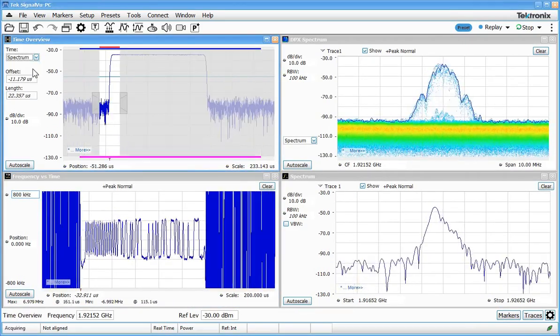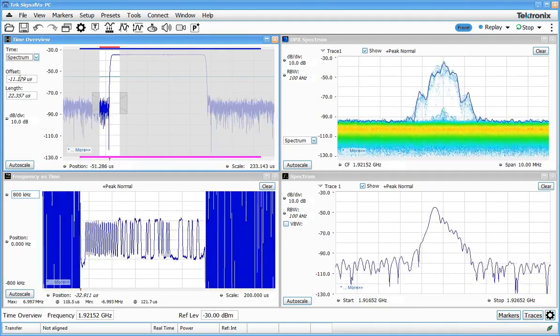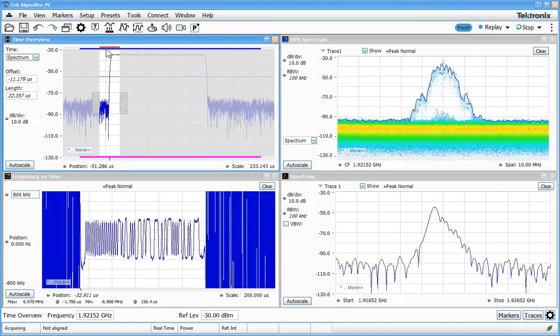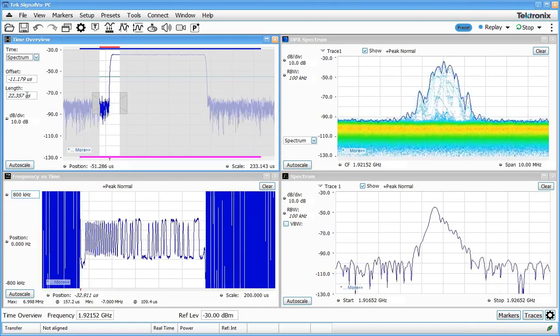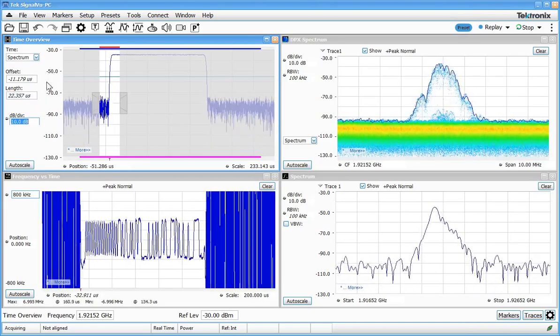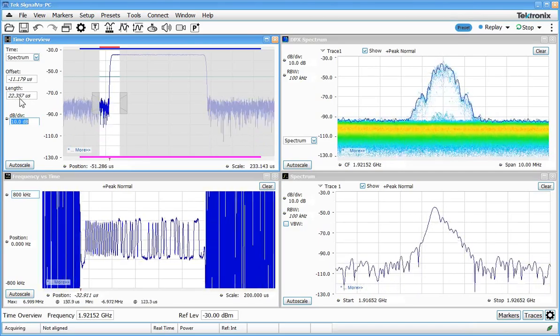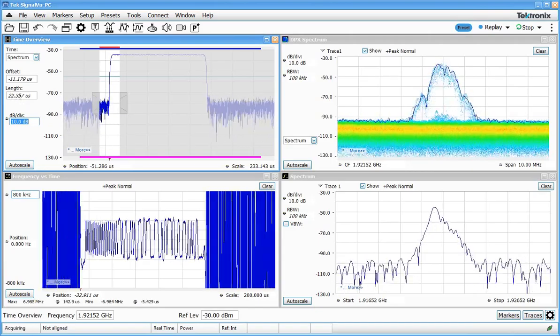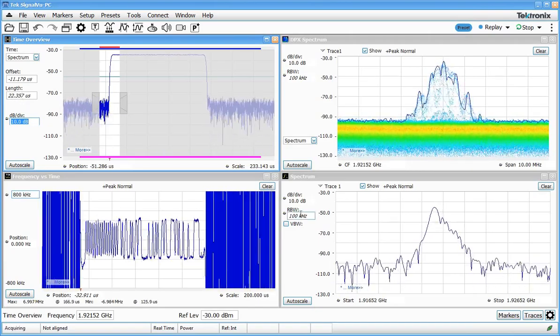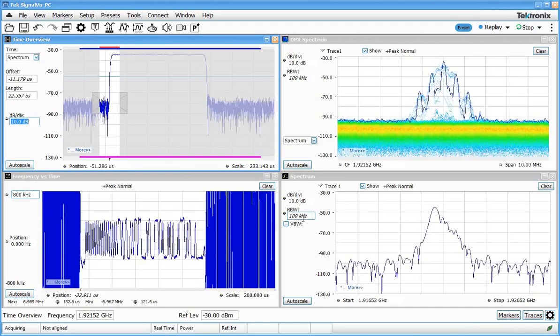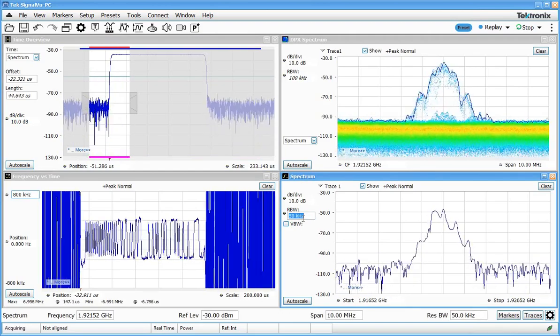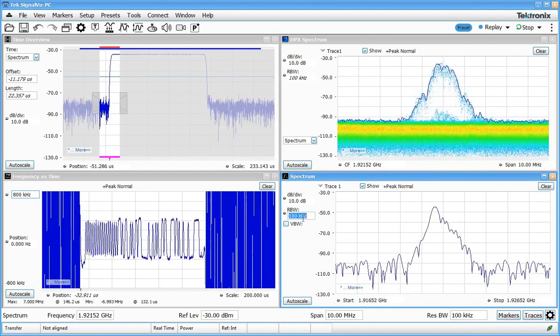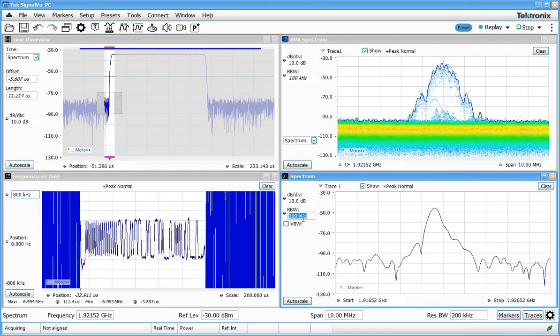Now the spectrum time works in a very similar way but there is a little bit of a twist. The offset certainly tells us where the spectrum measurement begins but the spectrum length you notice that the text for that right here is italicized. Italicized text in this application tells us that that value is coupled to something or was set by something else. In this case the spectrum length is actually driven by the resolution bandwidth that you asked for in the spectrum analysis. So if I change the resolution bandwidth say to 50 kilohertz, notice that the spectrum length has grown. If I increase the resolution bandwidth to say 200 kilohertz, notice that the spectrum length has decreased.